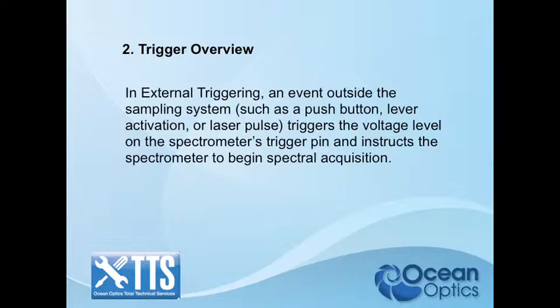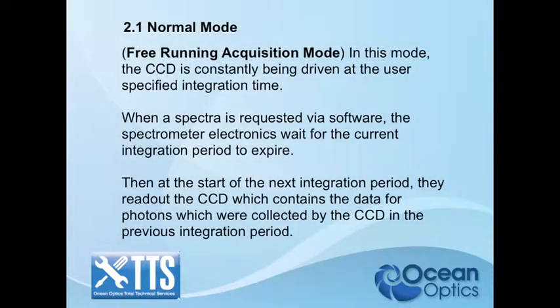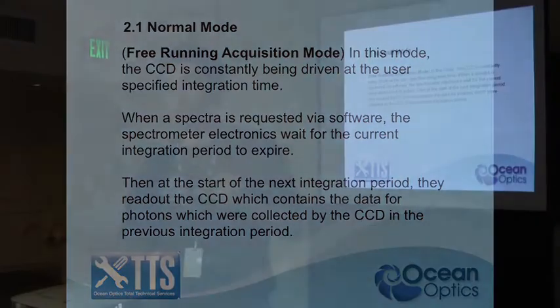We have normal mode, software trigger mode, external hardware trigger, external synchronization trigger, and external quasi trigger mode. Normal mode is when you plug a spectrometer and open the spectrometer suite — the spectrometer is just running in the background, acquiring spectra freely. We call it free running mode. If you have a five-second integration time, it's going to acquire and give you a new acquisition every five seconds.